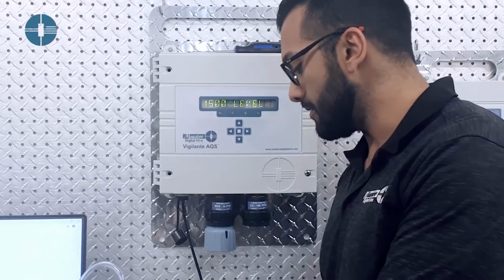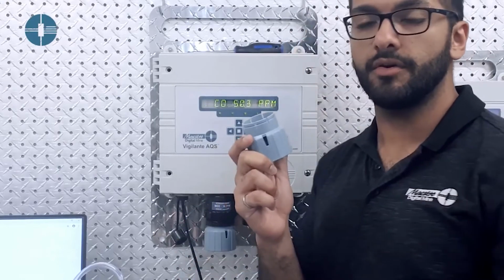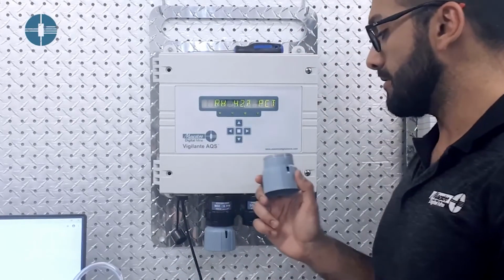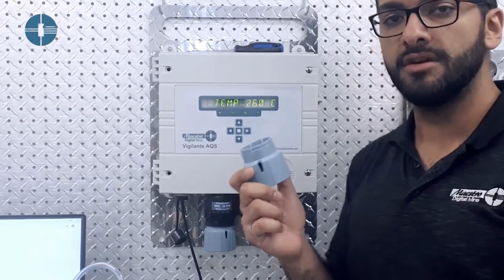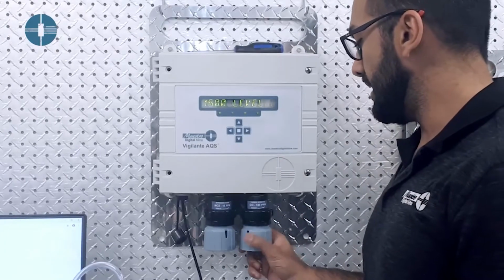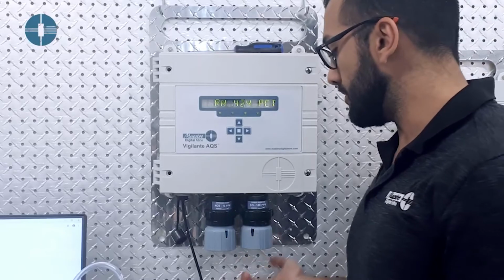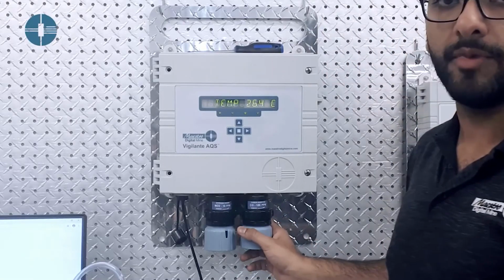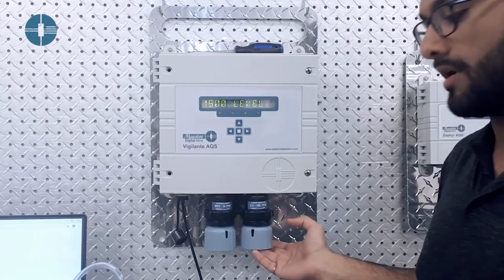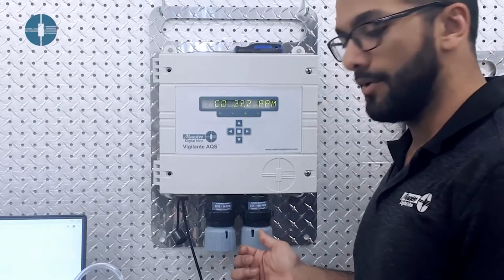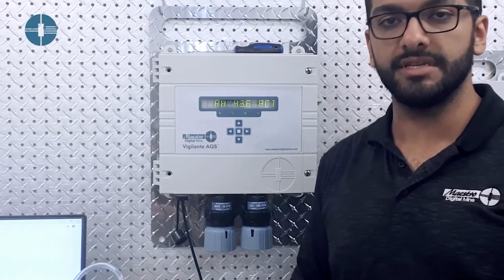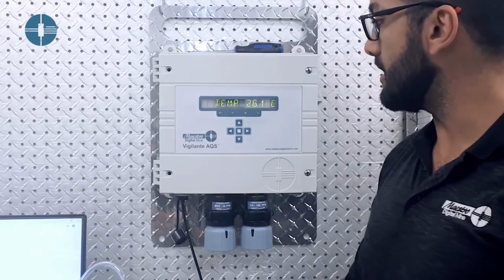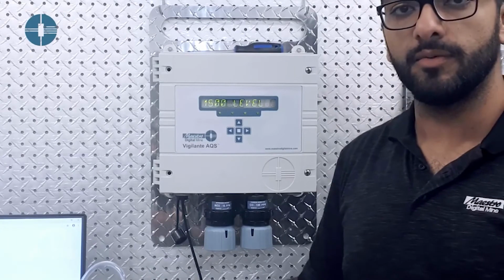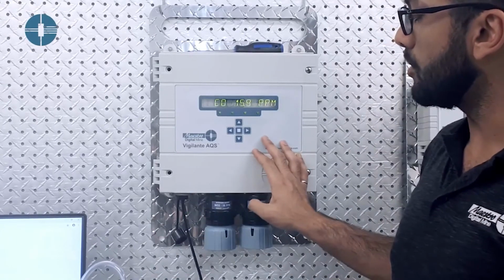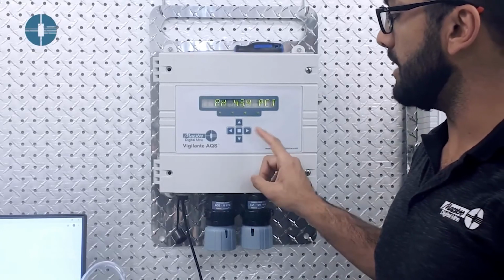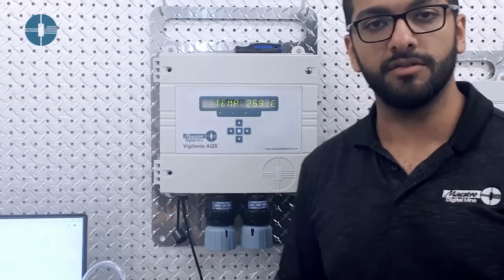And we're going to remember one important thing, which is to actually plug your calibration cup, also known as a gas sensor protector, back onto the gas sensor. And what that does is it protects it from any debris or any muck actually hitting the face of the sensor and blocking it as well, while allowing the gas to flow into the sensor. And that's your gas sensor calibration using the local method, and it's using the front keypad on the Vigilante as well.